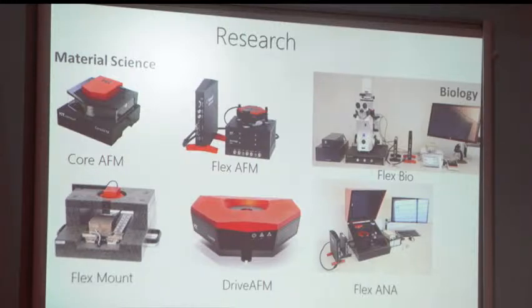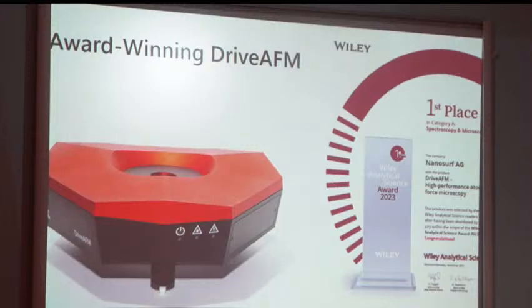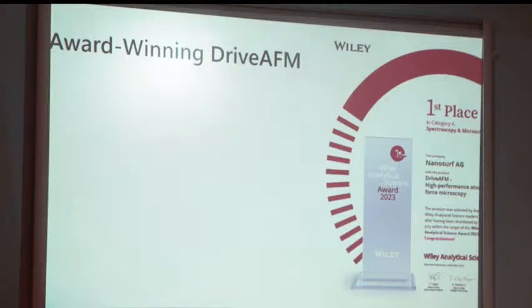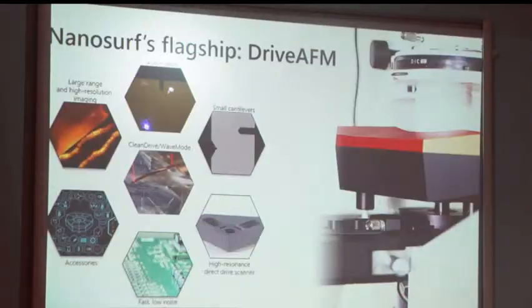All standard AFMs follow the same principle that I told you earlier. There is no difference between the principle from one AFM to another AFM. The good thing about Drive AFM is that we have recently won the first prize from Wiley as the best microscope in 2023. Drive AFM has a lot of features. The first feature is automated laser alignment. Just by clicking a couple of buttons in software, you can align the laser automatically.